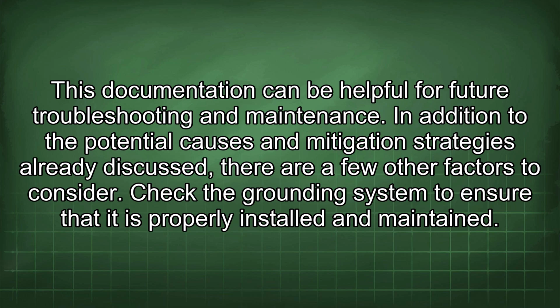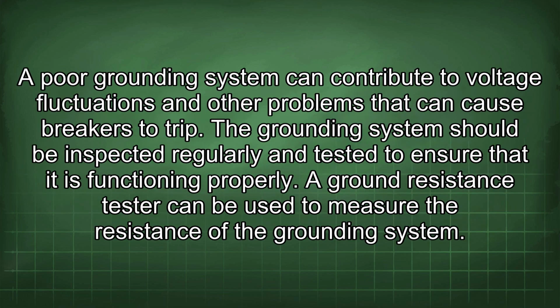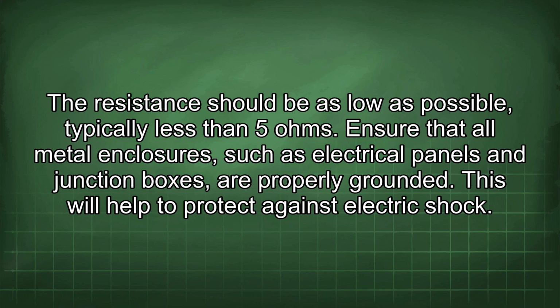In addition to the potential causes and mitigation strategies already discussed, there are a few other factors to consider. Check the grounding system to ensure that it is properly installed and maintained. A poor grounding system can contribute to voltage fluctuations and other problems that can cause breakers to trip. The grounding system should be inspected regularly and tested to ensure that it is functioning properly. A ground resistance tester can be used to measure the resistance of the grounding system. The resistance should be as low as possible, typically less than 5 ohms.